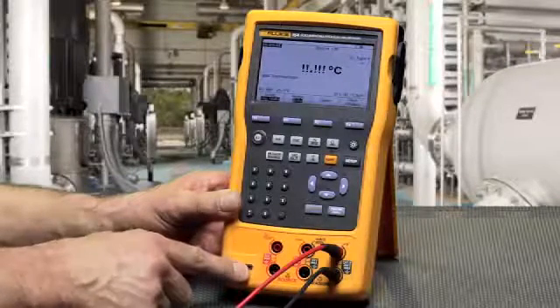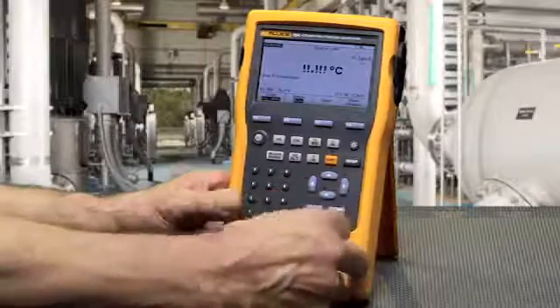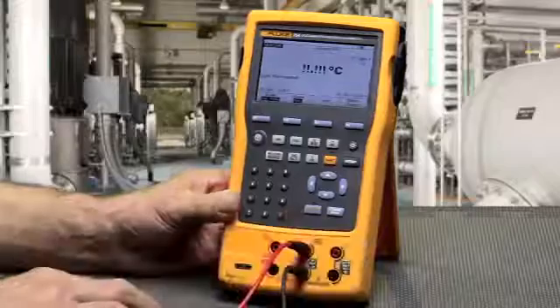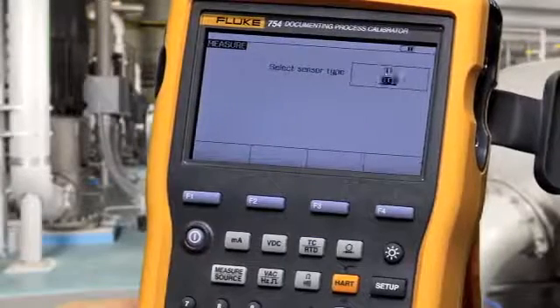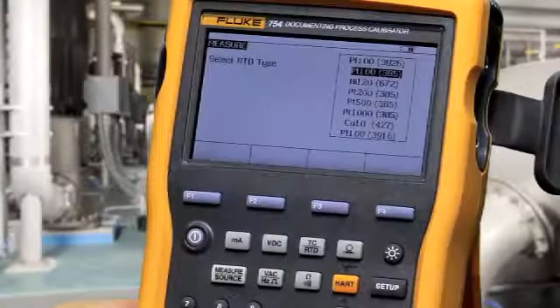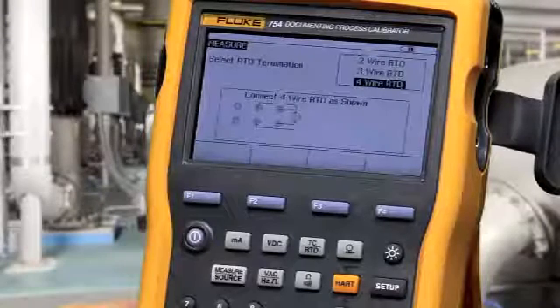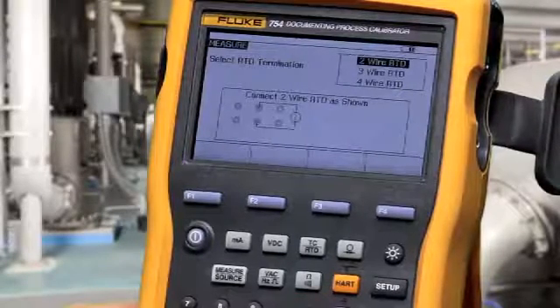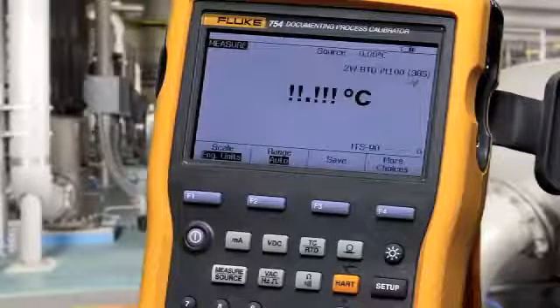Or to measure an RTD, make your connection here on the RTD measurement jacks. To measure RTD, move the cursor to RTD and press enter. Select the RTD type. Select two, three, or four wire connection diagrams according to your sensor. Press enter to make the selection.